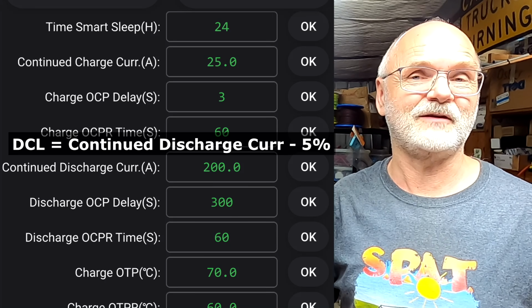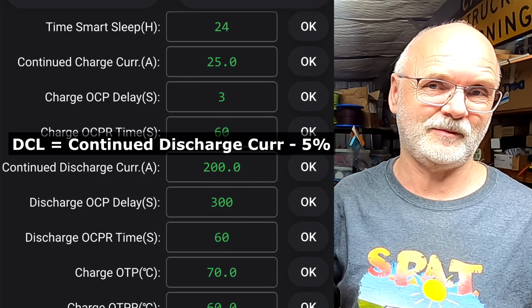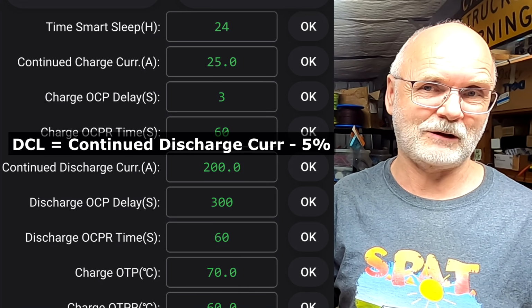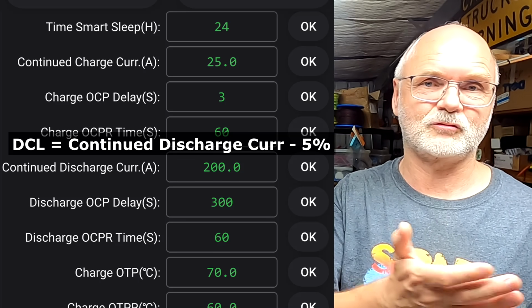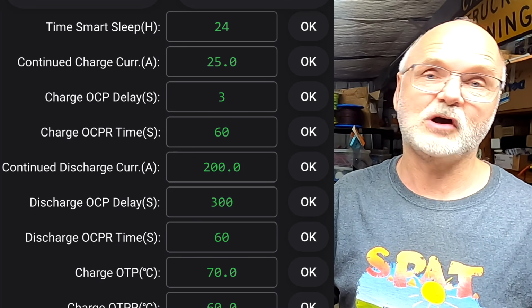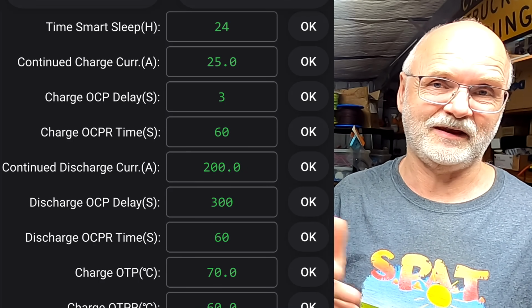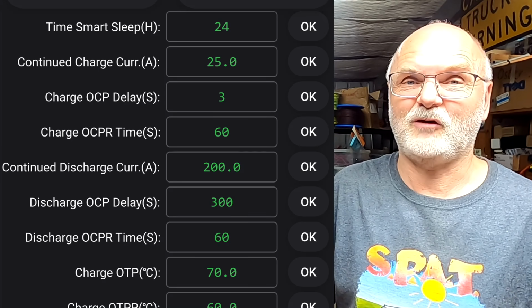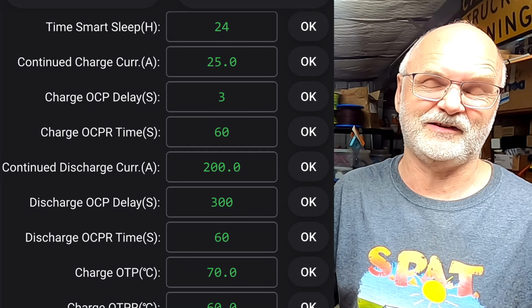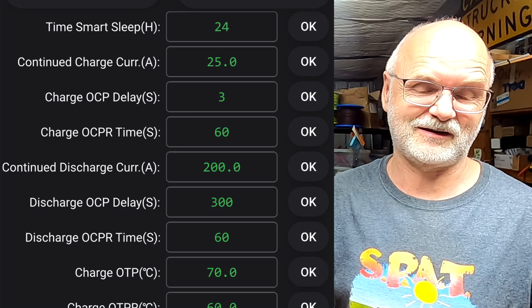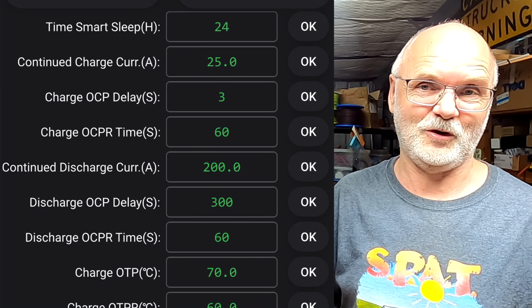And then we have the same for the continued discharge current, which is your DCL, your discharge current limit. It tells the inverter how much current it can pull from the battery. If the inverter needs more current to power your load, it takes the rest from the grid. Well, if you're off-grid, it will disregard this setting anyway, because there's only the battery as an energy source and it pulls as much as your load needs, regardless of what the BMS tells your inverter.